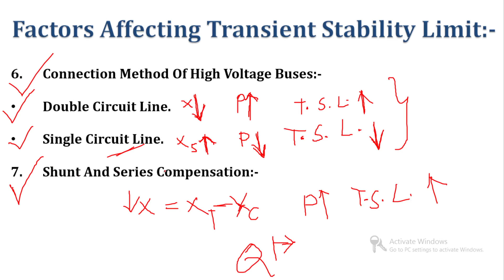Now the eighth point is single pole opening and reclosing. As we all know, many faults are not permanent in nature. Clear? Many faults in the system are not permanent in nature, and hence a single pole opening and reclosing arrangement is a reliable, cheap and economical solution. As we know, a line to ground fault is a common and most frequently occurring fault. So in single pole switching, the circuit breaker opens the faulty phase and the remaining healthy phases continue to supply the power. After clearance of the fault, that faulty phase can be returned to service after it has been de-energized for sufficient time.